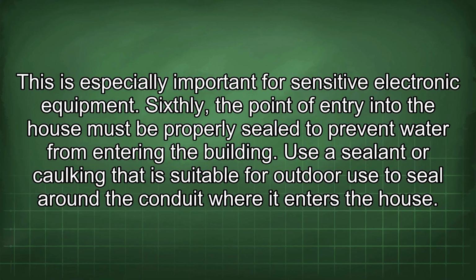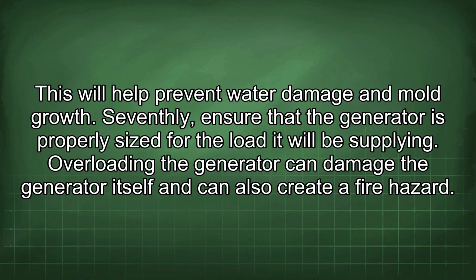Sixthly, the point of entry into the house must be properly sealed to prevent water from entering the building. Use a sealant or caulking that is suitable for outdoor use to seal around the conduit where it enters the house. This will help prevent water damage and mold growth.